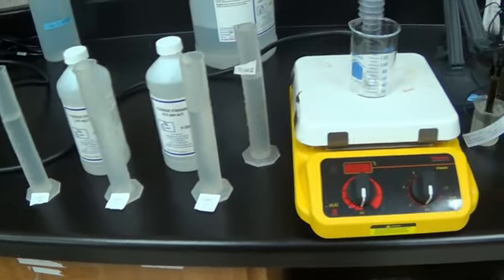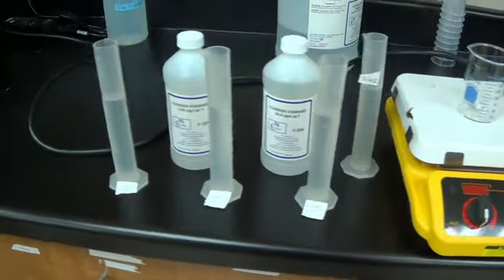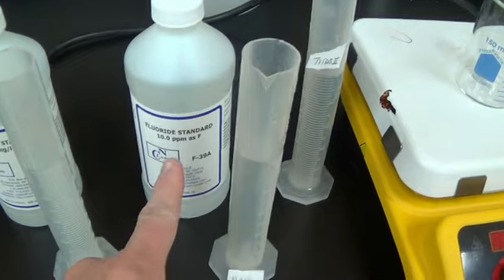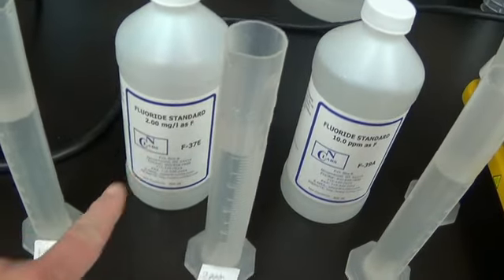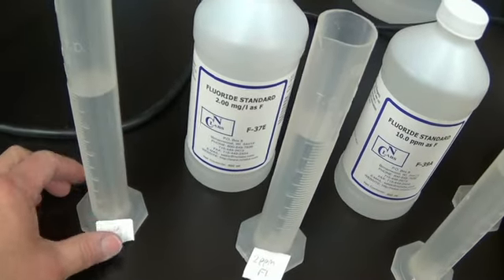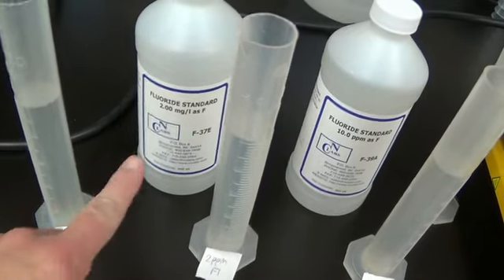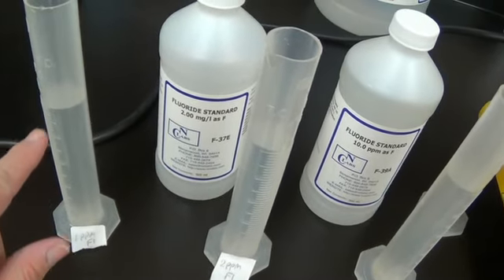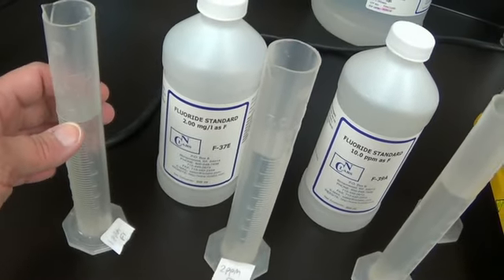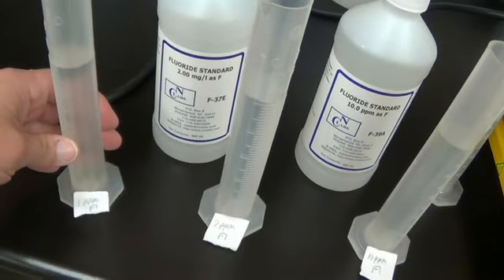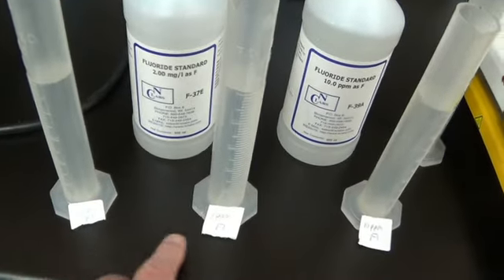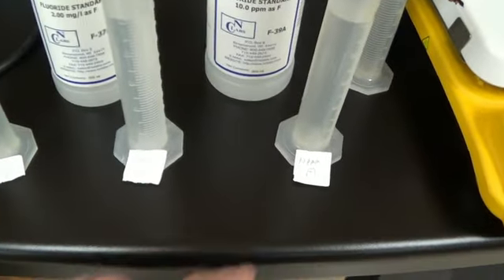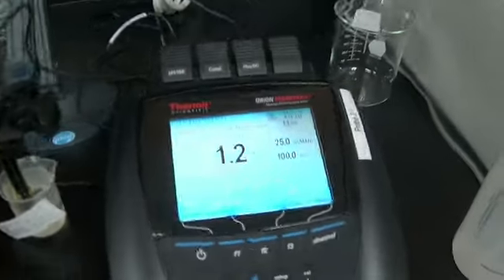So now I'm setting up for the calibration. I have a 10 standard, I have a 2 standard. I do not have a 1 standard, so I took 25 mils of the 2 standard and then diluted it up to 50 mils to make my 1 ppm. Now we are going to be changing this, so these will not be the standards you will likely be making, but that is how it is set up right now.